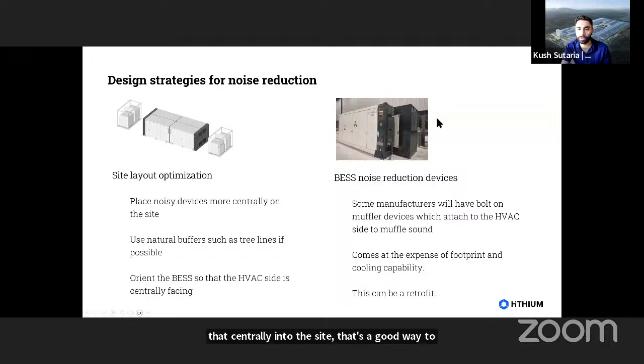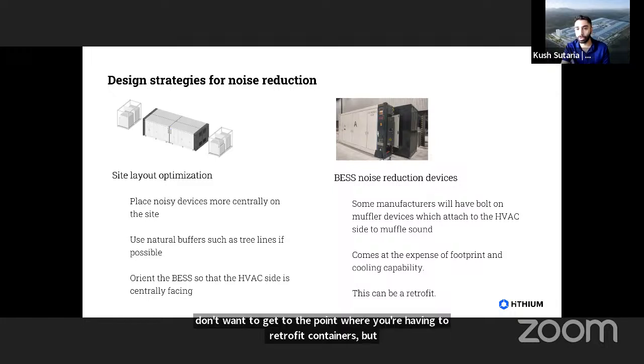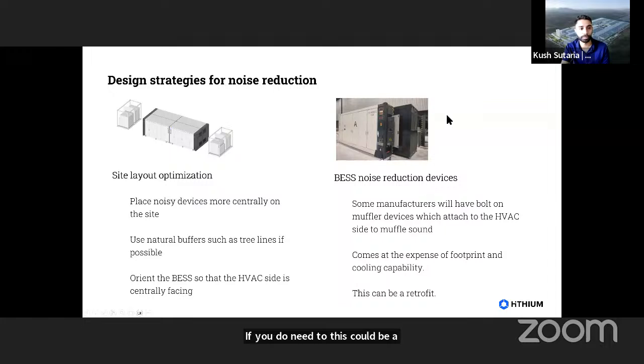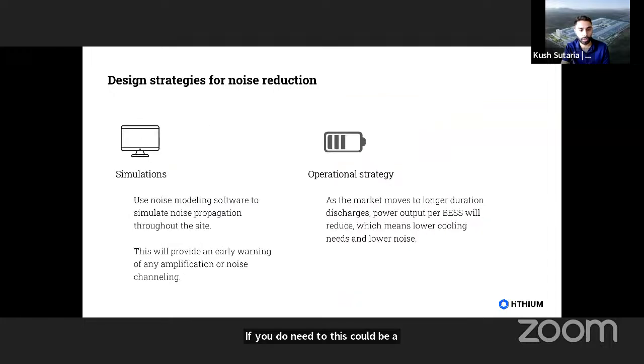We have a noise reduction kit that can be used. It kind of bolts onto the side of the container. This does increase the footprint area of the container, and cooling capability will also be slightly lower. So this could be a great option in colder climates, or for lower power projects. This can also be a retrofit afterwards. Obviously you don't want to get to the point where you're having to retrofit containers, but if you do need to, this could be a solution.